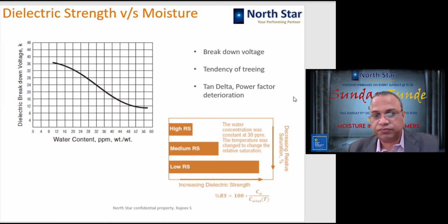Here I am showing one interesting correlation with the relative saturation, which we have studied in previous slides, and the dielectric strength. If you just read this statement, the water concentration was kept constant at 30 ppm, and only the temperature of the system was changed to change the relative saturation. As we have seen with this equation, only when the temperature is changing and nothing else is being changed, still the saturation value of percentage RS will change.